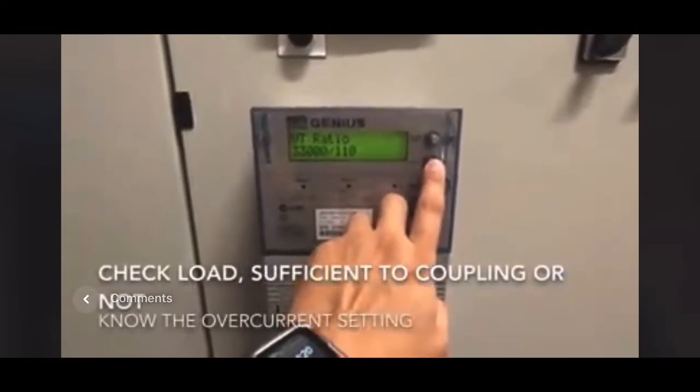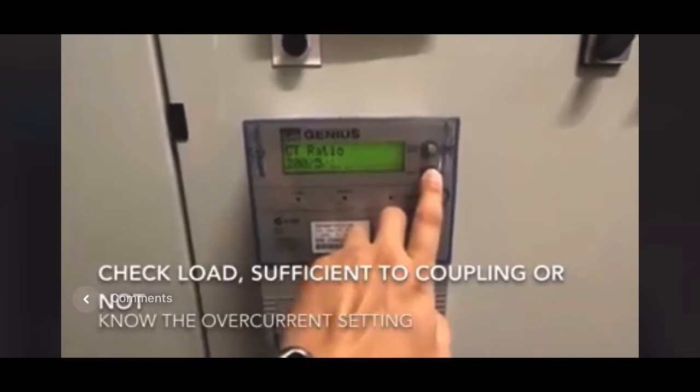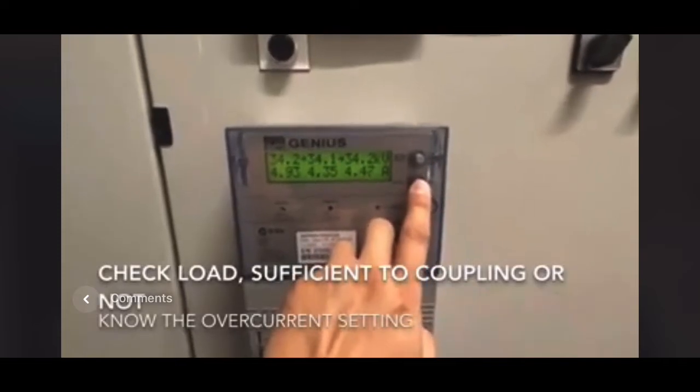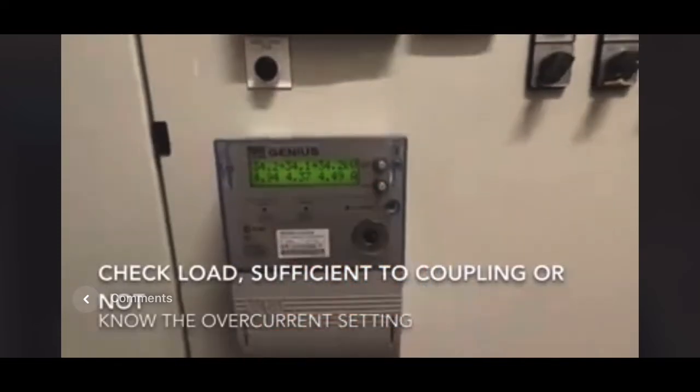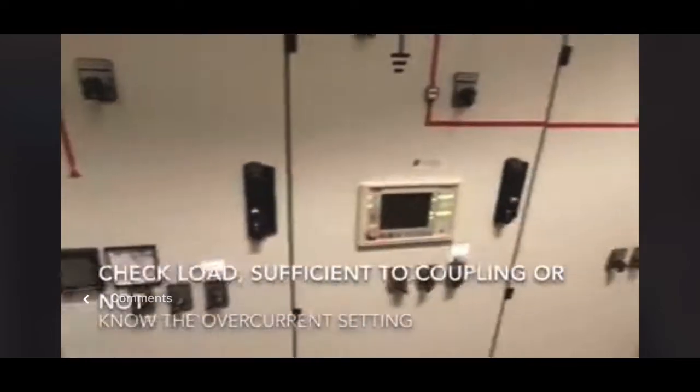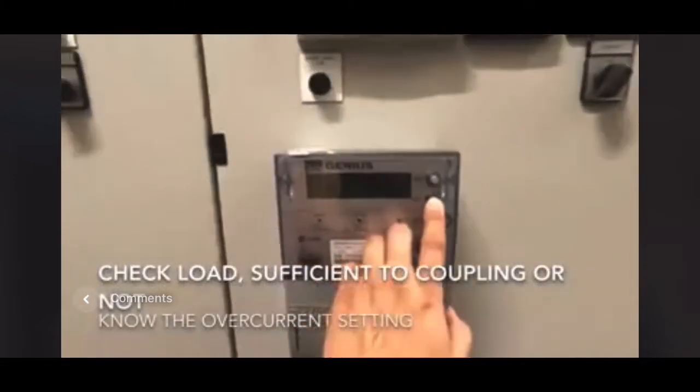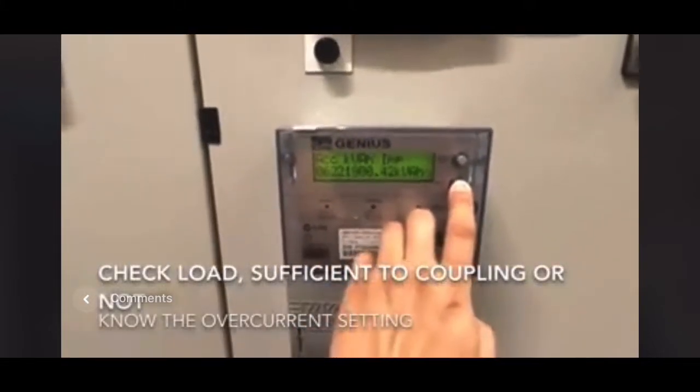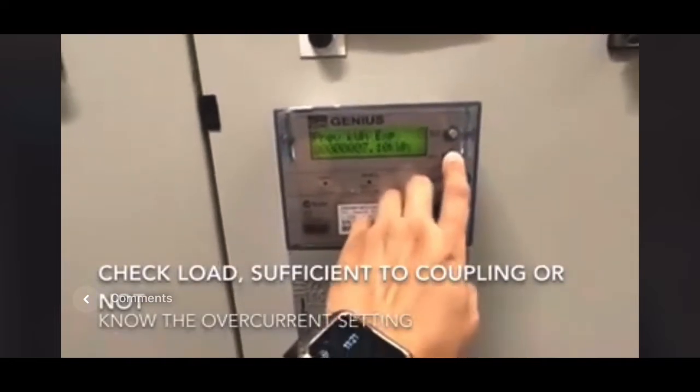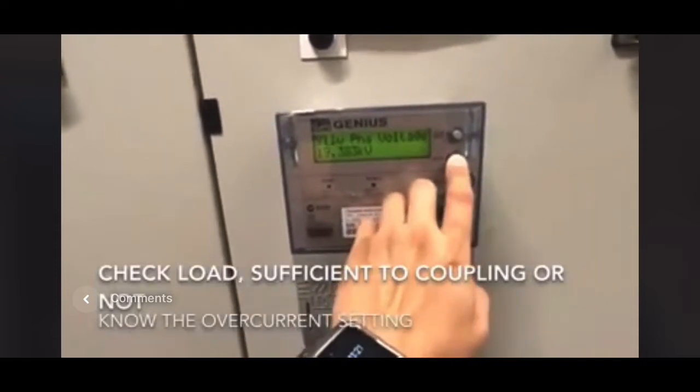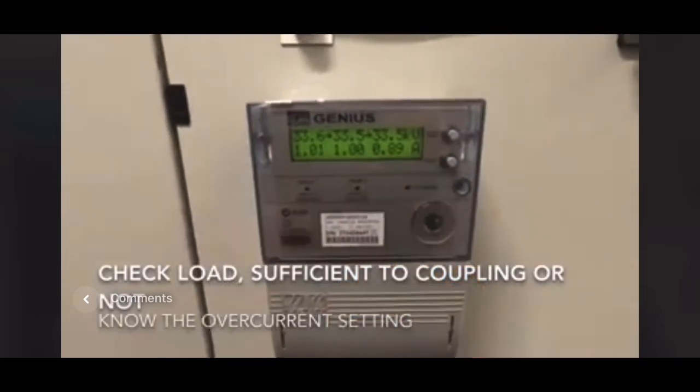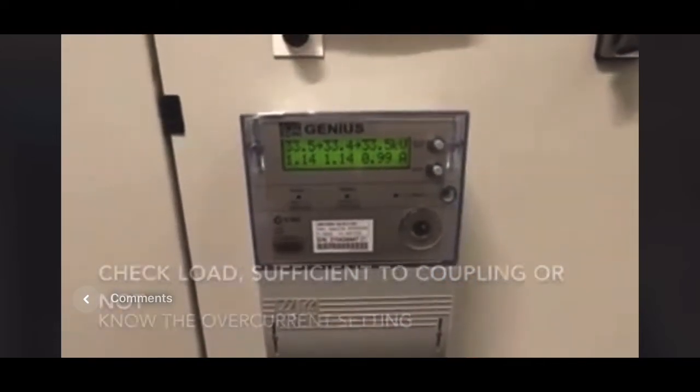Before you initiate any coupling, do check the loading factor. This is the Incomer number 2 loading factor. Currently we are using around 5A. And here is the Incomer number 1, which we are going to do the coupling here. Very minimum amp. Coupling should be not a problem.